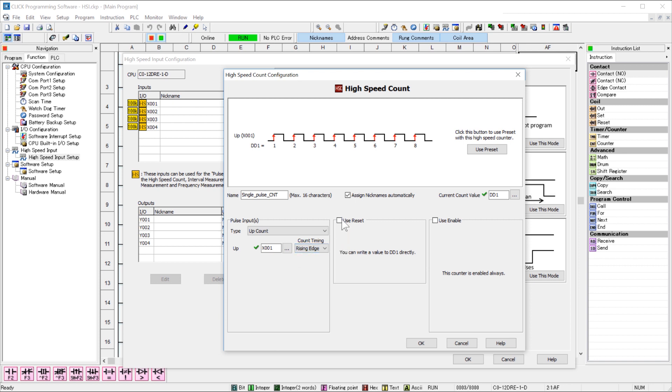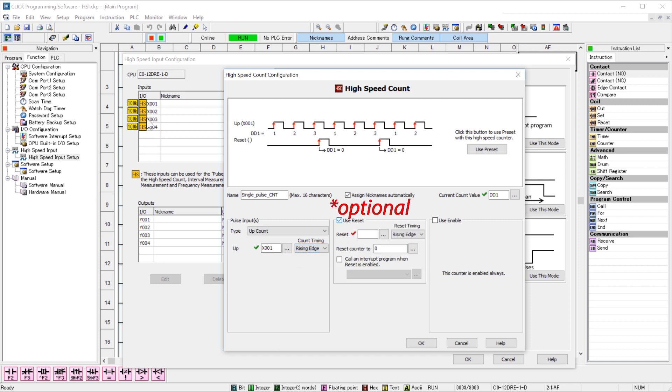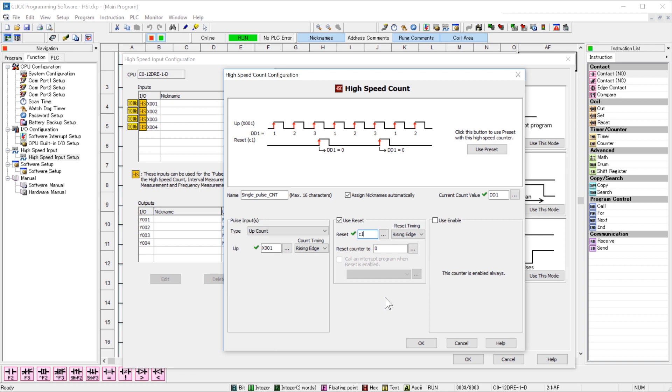Here are your reset options, and I am going to assign the internal coil to C1. When this bit turns on, it will reset the count to zero. If you use an internal coil, realize the timing of the reset will be dependent upon the scan time of the CPU.